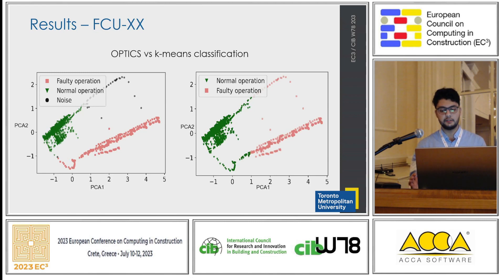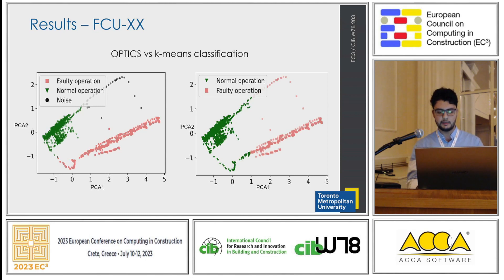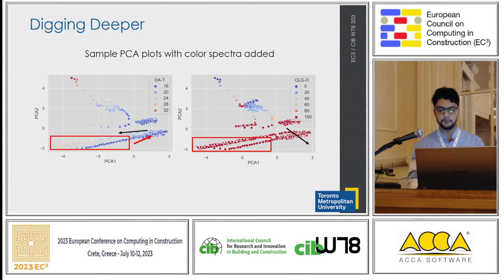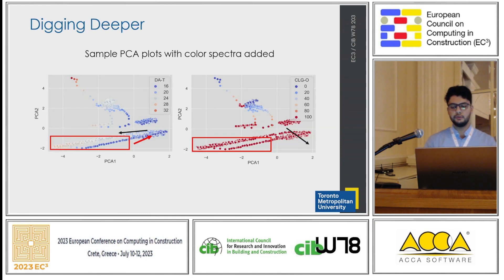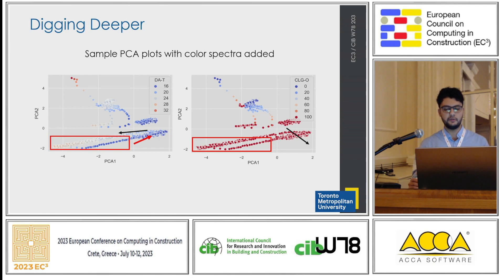However, with reviewing the broader data set, she identified that some faults were missed by both algorithms during the heating season — for example, from December 28 to December 29. In order to dig deeper, we used the Pearson correlation coefficient to find the correlation between the features.